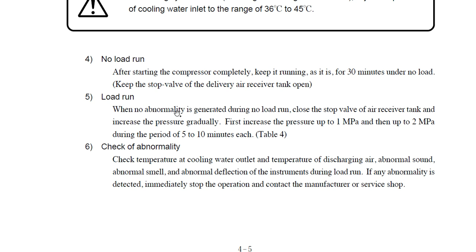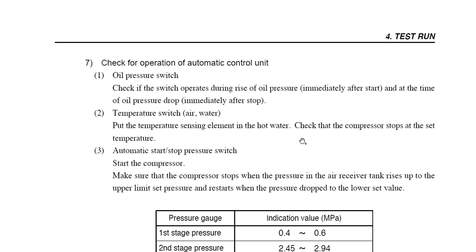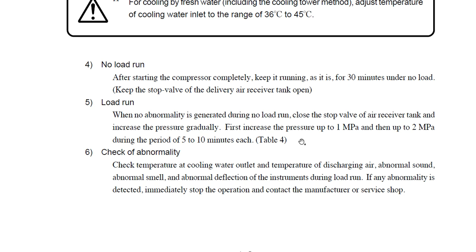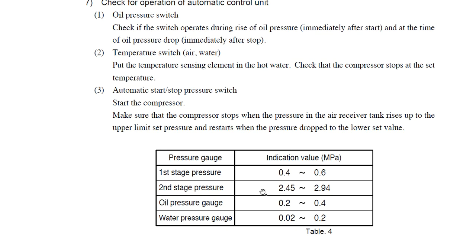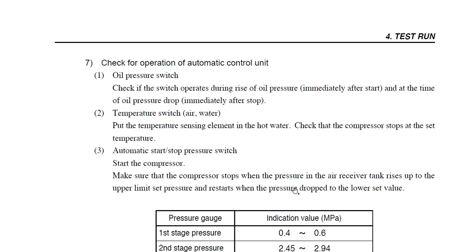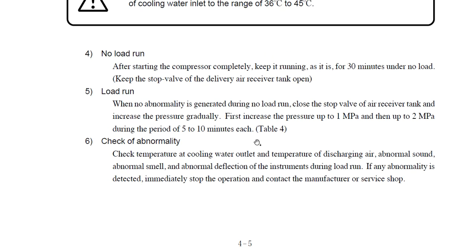Gradually, the first load will be to 10 bars, 1 megapascal here, and then we will increase to 2 megapascals, which is 20 bars, in a period of 5 to 10 minutes each. There is also a table available, a load table, and this table shows where our values are for the stages, which we will see later.